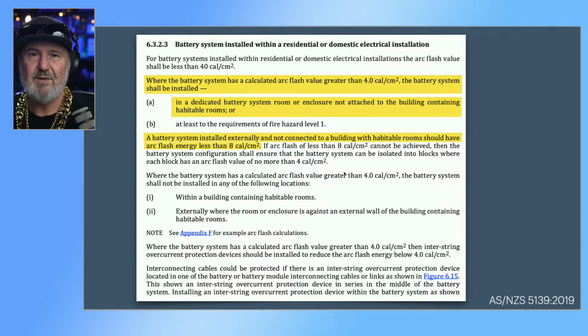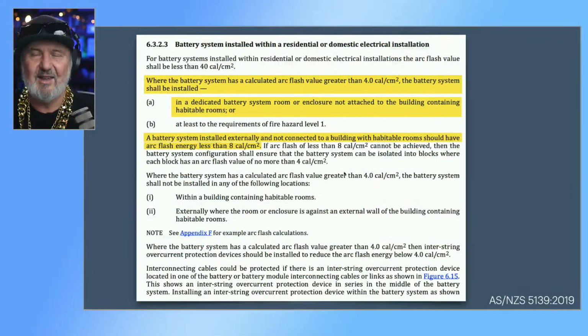Now, I've done a previous Toolbox Tech Talk on this, and if I can remember, I'll link it up here afterwards. Otherwise, you've got to just trawl through my previous ones. That's going to be hard work. And 40 cal per square centimetre is an incredibly high arc flash level. You're talking a full space suit, basically, one of those shiny suits, ear protection, hard hat. You basically look like you're going to walk into a furnace. So anything over 40 cal, not going to be in a residential installation.